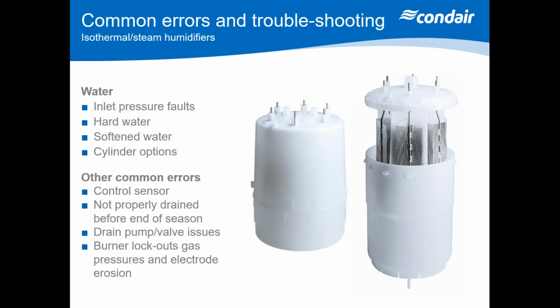So we touched on this a little bit in terms of inlet pressure for isothermal steam humidifiers, but pressure is very important onto those humidifier valves to make sure we're getting the correct flow rate. Hard water, as we talked about with the scaling, looking at cylinders, making sure they're the correct type.